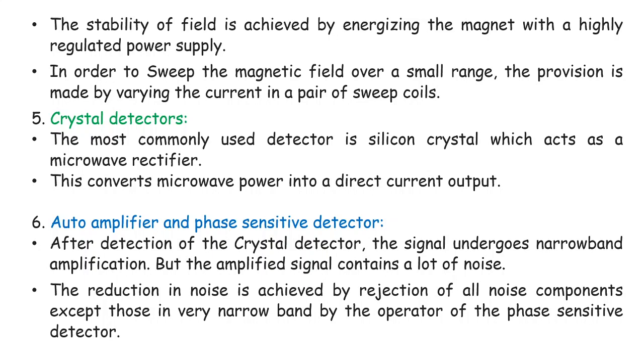An important component is the crystal detector. The most commonly used detector in ESR is the silicon crystal, which acts as a microwave rectifier. The detector converts microwave power into a direct current output — this is the basic function of any detector.